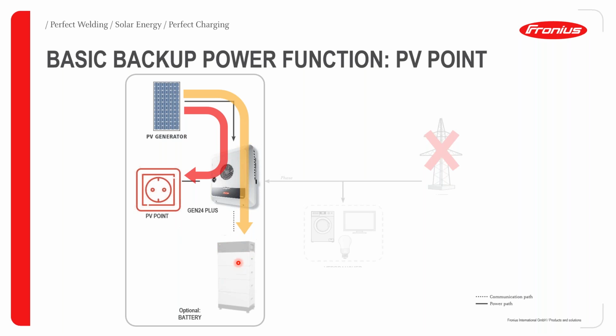At the same time, if you have a battery system connected to the Gen 24 and there's a grid outage, you could also have the excess energy that is available after feeding the PV point go to recharging the battery. Also, if the solar panels are not generating what is required by the PV point, then the deficit can be met by taking a bit of energy or power from the batteries to feed the PV point as well. Therefore, this ensures that you have a very basic and quick backup functionality with the Gen 24 Plus inverters, and it is actually one of the very few grid-tied inverters that can offer this kind of functionality, that they are able to function when there is a grid outage.